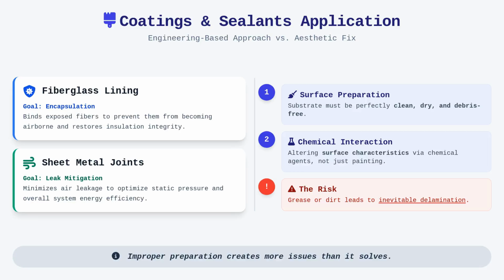With sheet metal, sealants are applied to minimize air leakage, which serves to improve the overall system's static pressure and energy efficiency. It is critical to recognize that you are not simply painting the inside of a duct. You are applying a chemical agent that alters the surface characteristics of the material. Therefore, you must ensure the substrate is perfectly clean, dry, and free of dust or debris before any product touches the surface. If the surface is compromised by grease or residual dirt, the sealant will inevitably delaminate over time, potentially causing more issues than it solves.